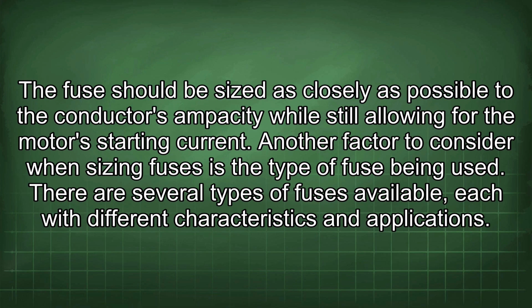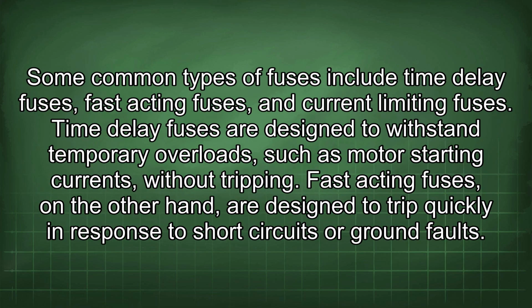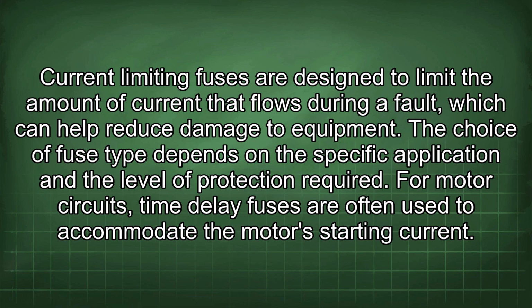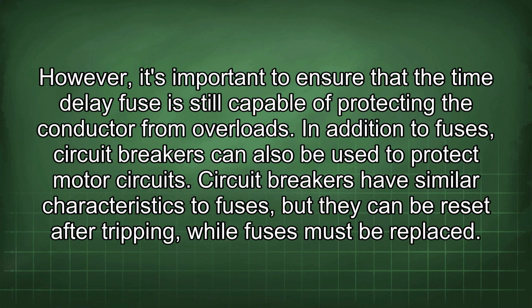There are several types of fuses available, each with different characteristics and applications. Some common types of fuses include time delay fuses, fast-acting fuses, and current-limiting fuses. Time delay fuses are designed to withstand temporary overloads, such as motor starting currents, without tripping. Fast-acting fuses, on the other hand, are designed to trip quickly in response to short circuit or ground faults. Current-limiting fuses are designed to limit the amount of current that flows during a fault, which can help reduce damage to equipment. The choice of fuse type depends on the specific application and the level of protection required. For motor circuits, time delay fuses are often used to accommodate the motor's starting current. However, it's important to ensure that the time delay fuse is still capable of protecting the conductor from overloads.